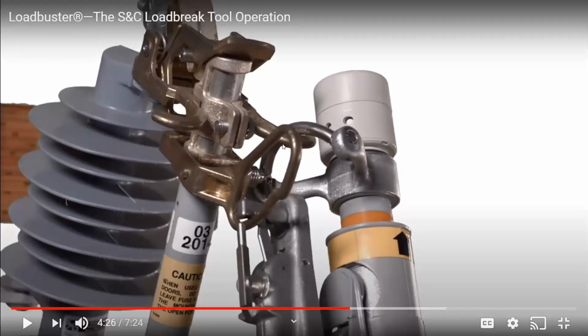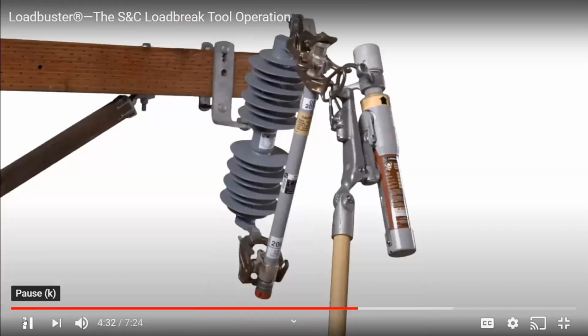Okay. So right now, the way it has it, I still have current flow that's going through the fuse. As soon as I start to make the pull motion on this stick, this is going to start to open and clear the top of the switch, but I'm still going to have current flow from here to here to here until I make the full motion and break load inside the tube. The Loadbuster tool is now connected across the upper contact of the SMD20 power fuse.